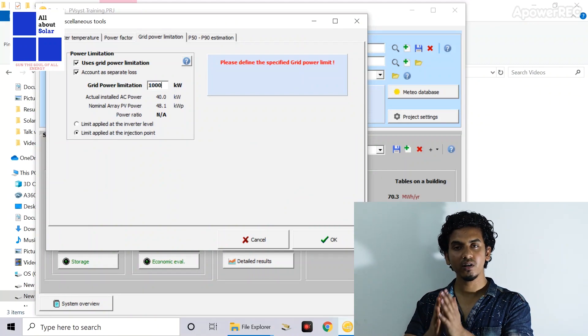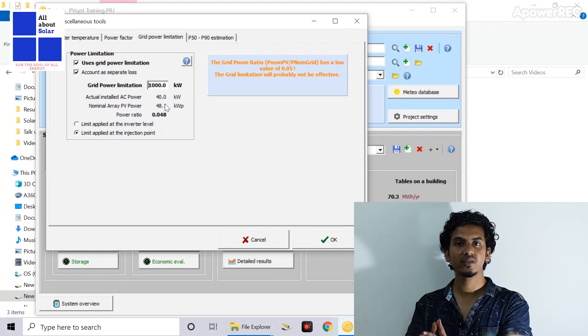Let's say you have a 1,200 kilowatt DC plant — that means a 1.2 megawatt DC plant — and you use a 1 megawatt AC inverter, which means 20 percent overloading, so your plant can export 1 megawatt of power. In that case, to restrict that extra power injection to the grid, you can restrict or mention that power limitation in this step.